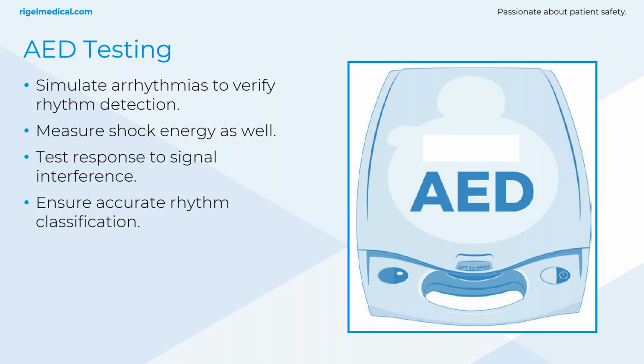And if you ever use an analyzer and you're testing a defib and you introduce that noise interference, you'll actually see the noise come up at first on the screen, and eventually what it should do is filter that noise out. And that's just mimicking real life scenarios where you might find mains interference in the hospital or in any sort of public space. So the AED must be able to analyze that rhythm correctly even through the noise that may be occurring.